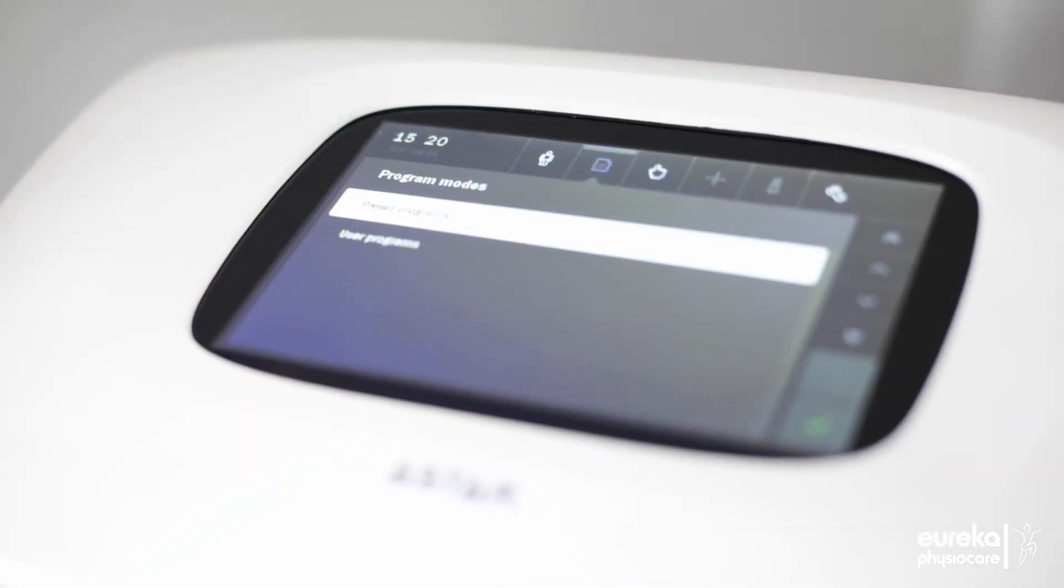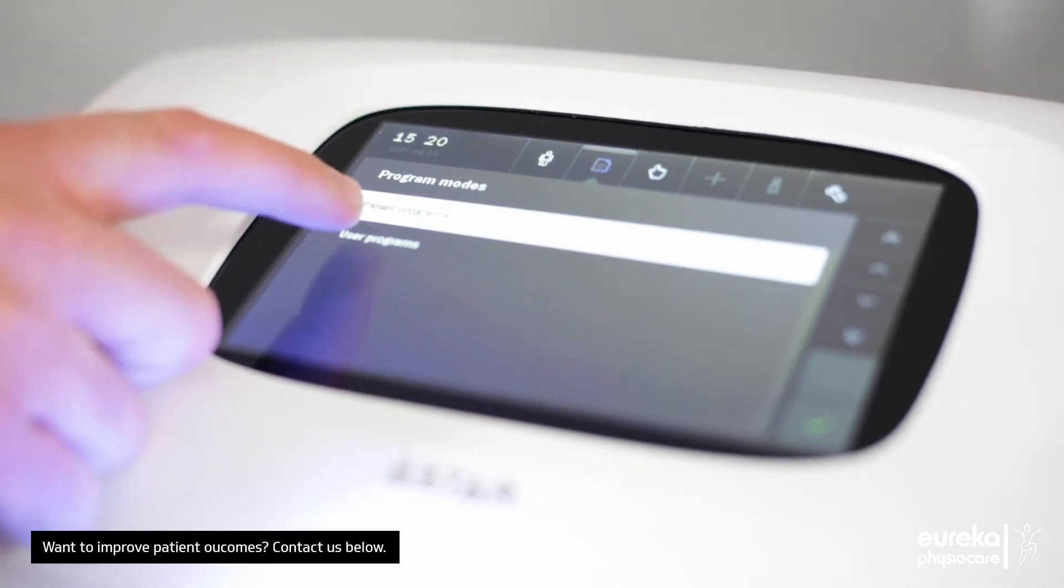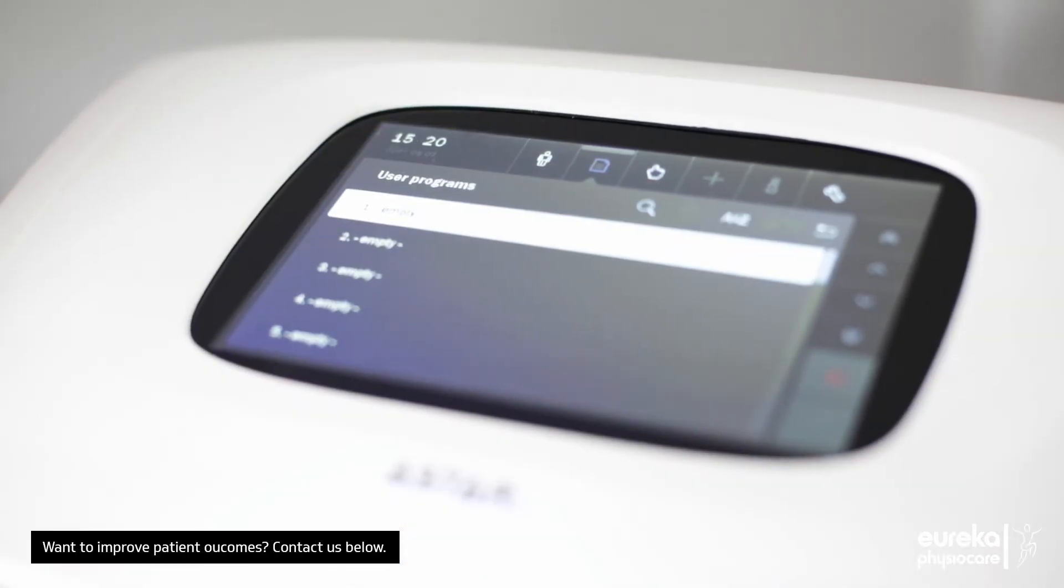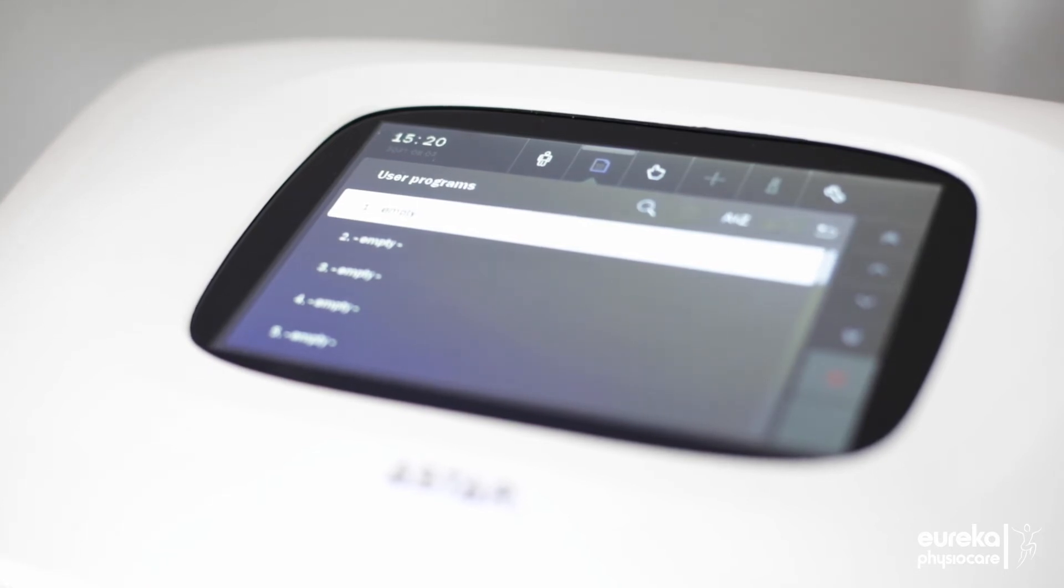So within the program modes there is also the option to save up to 50 of your own preset user programs which can then be accessed using the user programs menu. This means that you can save your own programs and parameters based on either a particular patient or particular condition that you find works best from your experience.